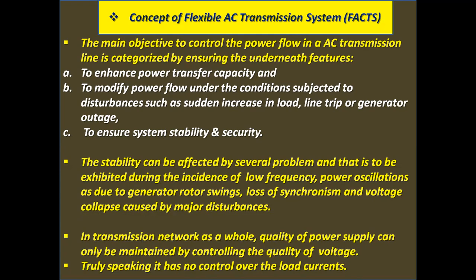The stability can be affected by several problems, and that is exhibited during the incidence of low frequency power oscillations due to generator rotor swings, loss of synchronism, and voltage collapse caused by major disturbances. In a transmission network as a whole, quality of power supply can only be maintained by controlling the quality of voltage. Truly speaking, there is no control over the load currents.